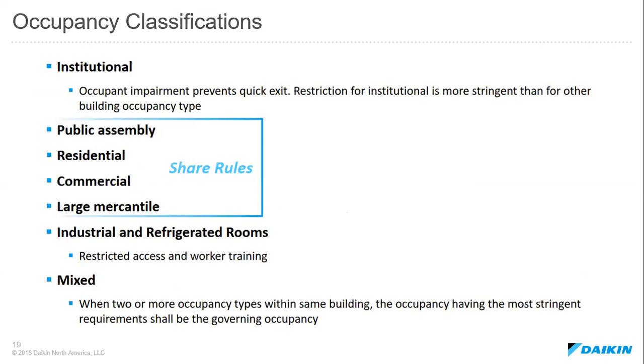So with ASHRAE 15, there are a lot of different occupancy classifications. And if I were to break down these occupancy classifications, a lot of them are related to institutional, which is important for occupant impairment and with regard to preventing or allowing a quick exit in the case of emergencies. Other occupant classifications are for public assembly areas, such as churches, residential, commercial, such as office and retail, and then also for large mercantile. There are also occupancy classifications through ASHRAE 15 for industrial and refrigerated rooms, which may restrict access and provide a requirement for certain alarms and other things, which I'll mention later in our presentation.